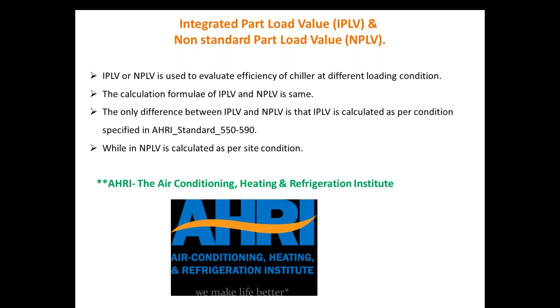So why are IPLV and NPLV calculated? Because we already have COP and EER to evaluate the performance of a refrigeration system. Then why IPLV and NPLV? COP and EER are calculated based on the full load capacity. Suppose I am using a 1 TR refrigerator; when I calculate COP, I will assume that the refrigerator is fully loaded. Clear? But in the real world, in day-to-day life, chillers, particularly air conditioning devices, hardly ever run at their full capacity. Most of the time, they are partly loaded. So the value you obtain from COP and EER and the actual performance are different, right?